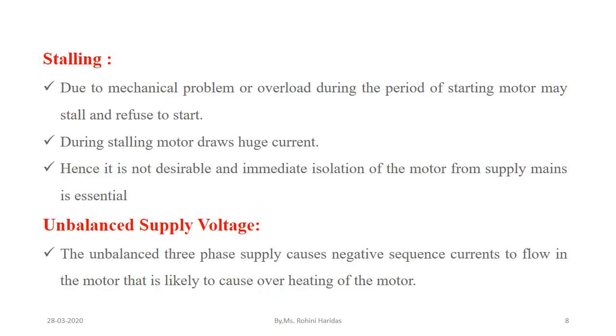The next abnormal condition is stalling, which occurs due to mechanical problems or overload. During the starting period, the motor may stall or refuse to start. During stalling, the motor draws a huge amount of current, which is not desirable, and immediate isolation of the motor from the supply mains is essential.